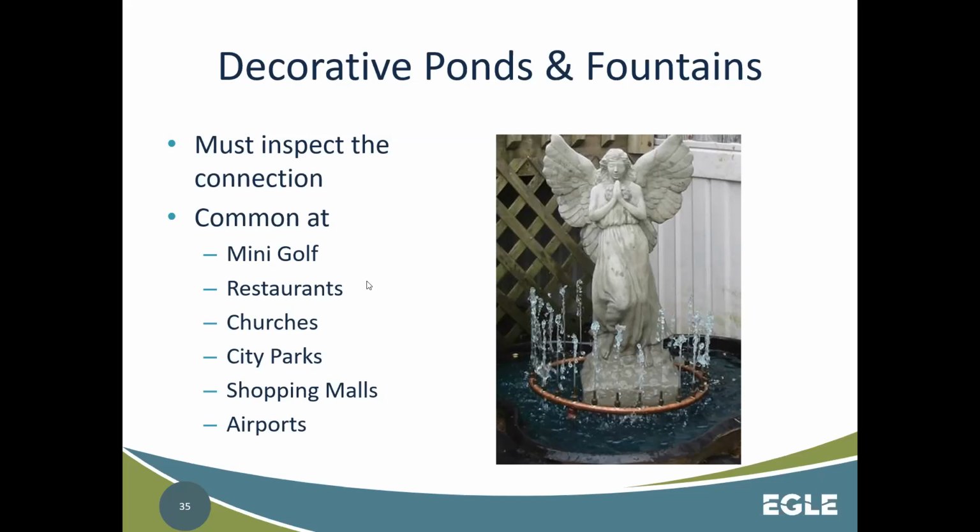We have, so there was an example actually from 2014. There's a village that was struggling with some BACT positives, total coliform positives. And what had happened is a hose had been connected to a yard hydrant and run out to one of these fountains to fill it up. So normally the fountain was actually separated, but the hose had been left in place while the fountain was filling and actually ended up getting flooded. Its outlet ended up being below the water level.